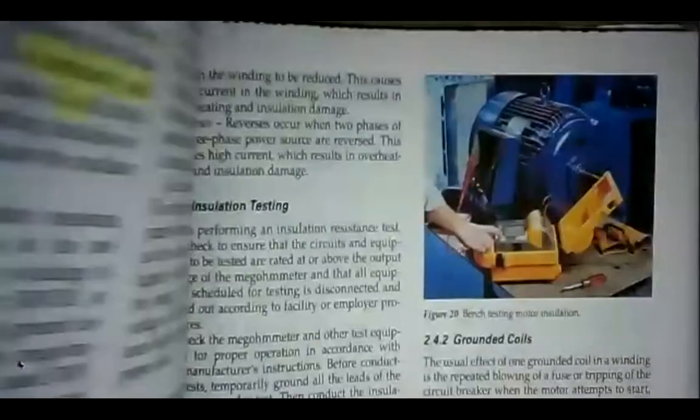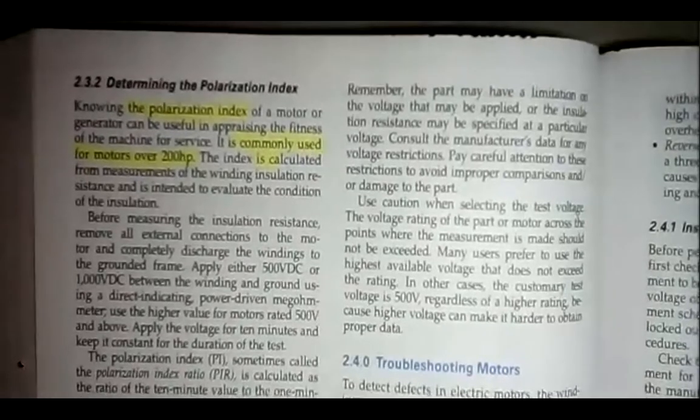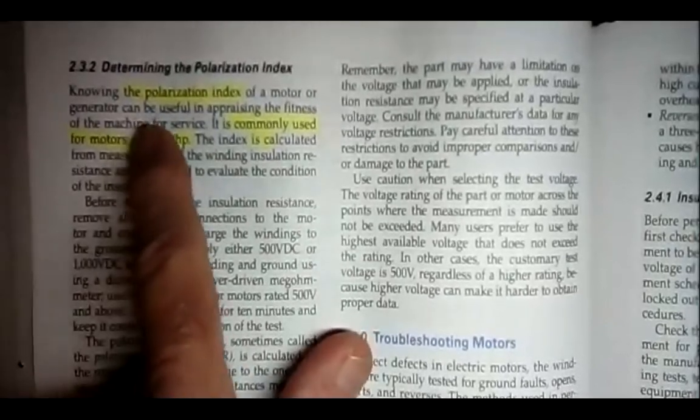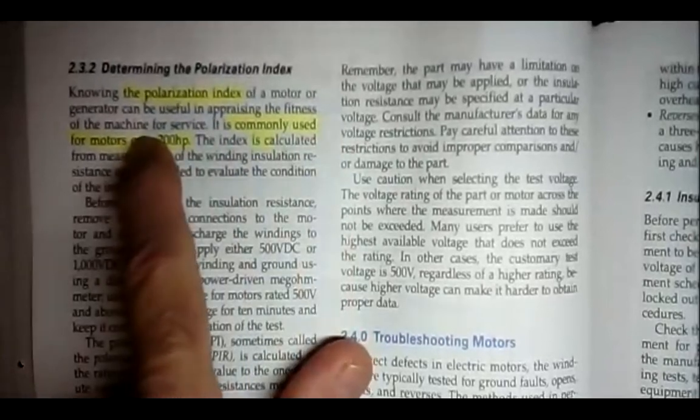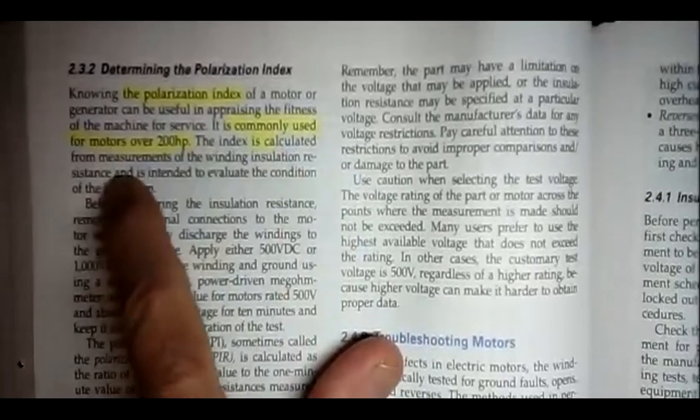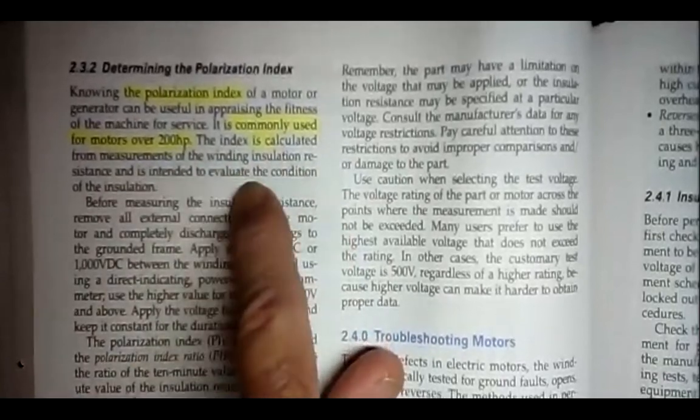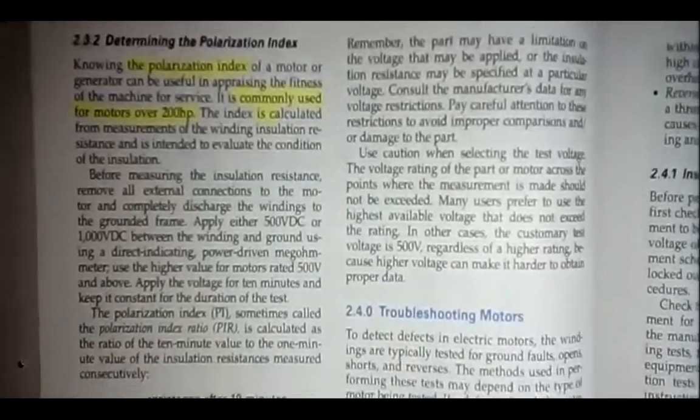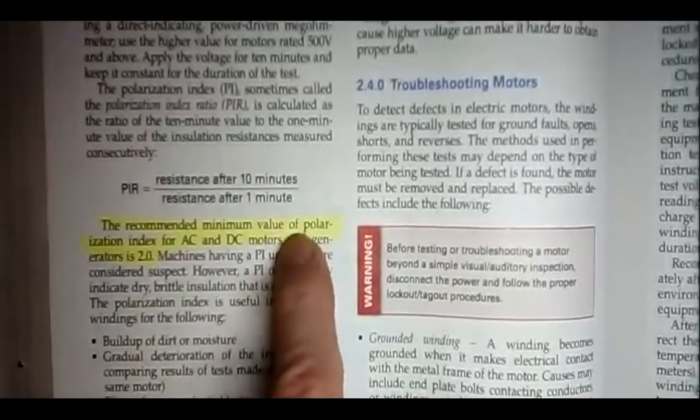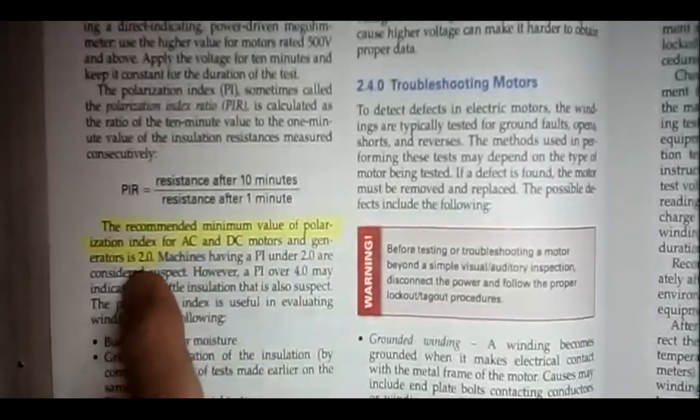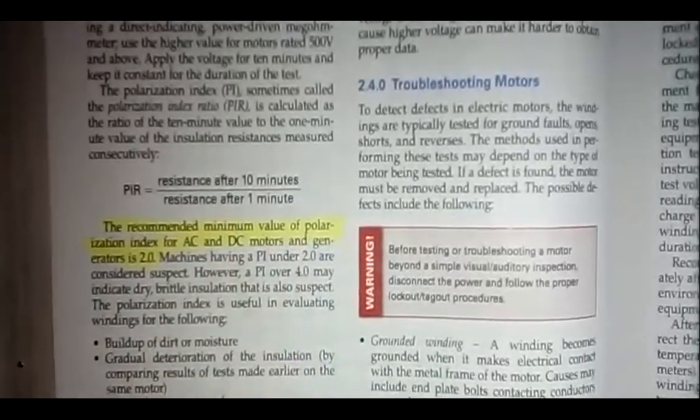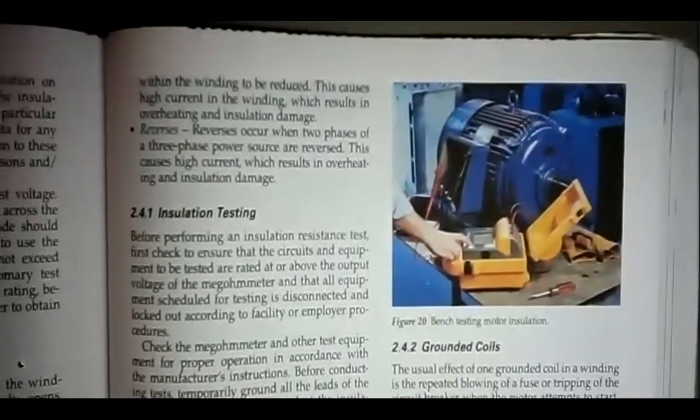And on page 22, on the left-hand column, determining the polarization index. Knowing the polarization index of motor or generator can be useful in appraising the fitness of the machine for service. It's commonly used for motors over 200 horsepower. The index is calculated from measurements of the winding insulation resistance and is intended to evaluate the condition of the insulation. So, it's the polarization index. Basically, you take the resistance after 10 minutes, divide that by the resistance after a minute. Recommended minimum value of polarization index for AC and DC motors is two. You should have twice the resistance after 10 minutes as you do after one minute. So, you would take those two readings and hopefully you've got twice the resistance.